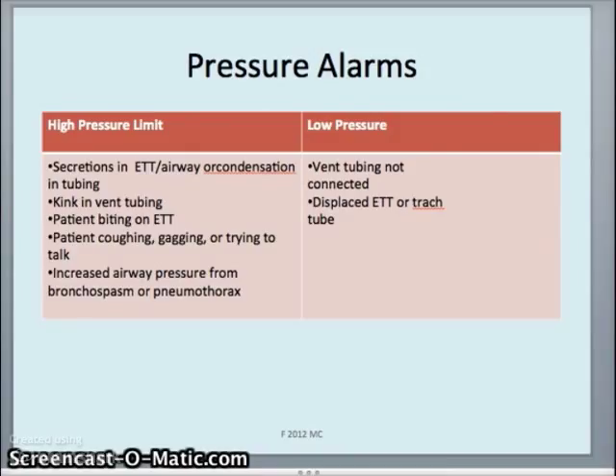Sometimes there's what we call overcondensation in the tube. So remember that the air is humidified. Sometimes that mist comes together and pools in some of the tubing, and it makes like a little puddle in the tubing, for lack of a better word, and it will impair the ability of the air to move smoothly, and you'll have a high pressure alarm go off, okay? All that needs to be done is to get rid of that condensation, and you'll be fine.